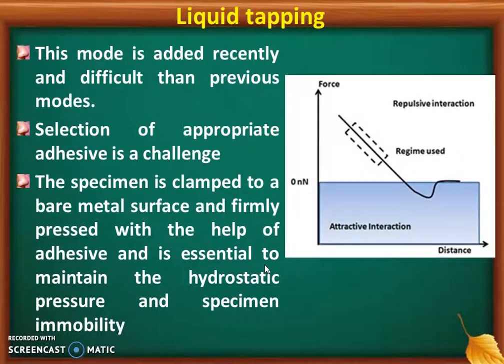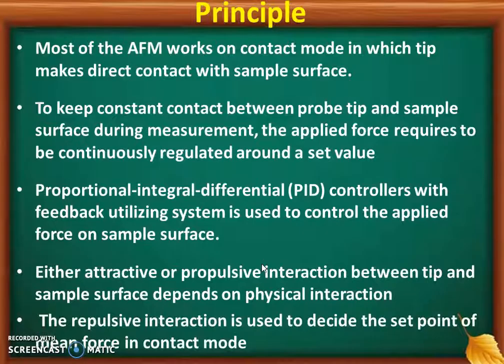Now, liquid tapping mode was added recently because this is a very latest developed mode. Selection of appropriate adhesive is a challenge because an appropriate adhesive is required to work in liquid tapping mode. The specimen is clamped to a bare metal surface and firmly pressed with the help of adhesive, and this is essential to maintain the hydrostatic pressure and specimen immobility.